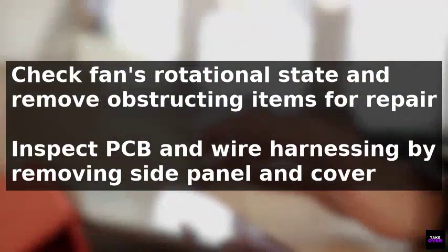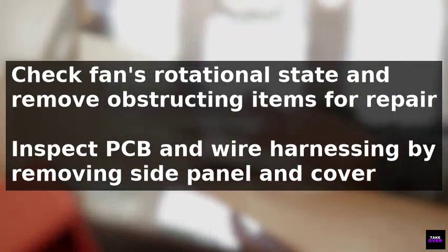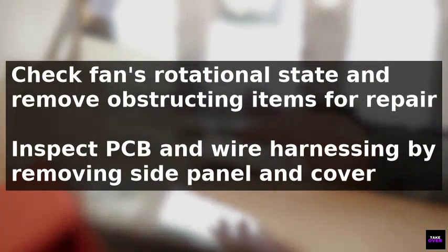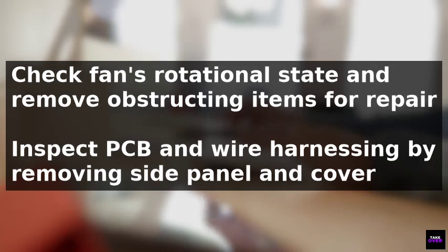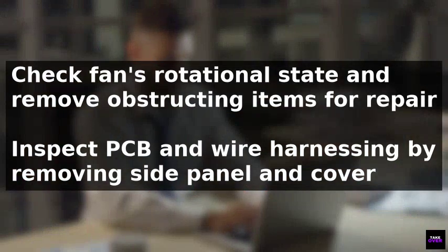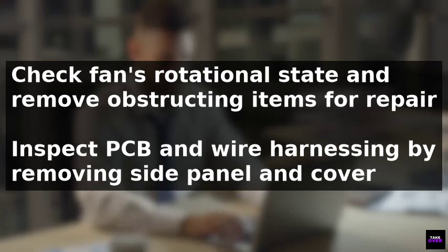Additionally, inspect the PCB and wire harnessing by removing the indoor unit's side panel and unmounting the control box's cover to access the PCB board. Disconnect the fan harness from the PCB. Turn the unit off, and measure the phase-to-phase resistance across the terminal block where the fan harnesses connect.